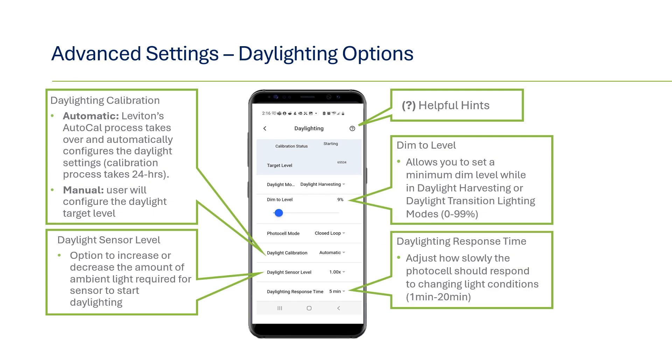For daylight calibration, you can select the device to do it automatically or you can do it manually. For automatic calibration, the sensor will use Leviton's AutoCal process, which will hold the lights on for 24 hours to calculate the target value based on only artificial lighting. If manual calibration is selected, you can select the target value yourself — the page will display the current light lux value that the sensor is seeing. Once the target is set, the daylighting will kick in instantly, with no need to wait 24 hours. For daylight harvesting applications, you can select a dim to level so that even if a space is flooded with an extraordinary amount of natural ambient light, the luminaire lighting never dips below this value.